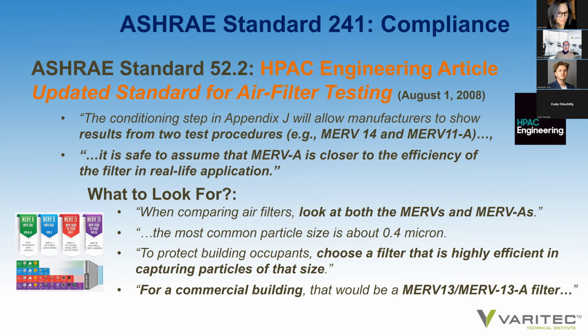There was an interesting article in HPAC Engineering published when the updated 52.2 standard was initiated, published on August 1st of 2008. It goes on to say that the conditioning step in Appendix J will allow manufacturers to show results from two test procedures, MERV 14 and MERV 11A. And by the way, Appendix J to 52.2 is a voluntary test procedure. It is not a necessary test procedure. Well, it was until 241 has issued the language that it has.